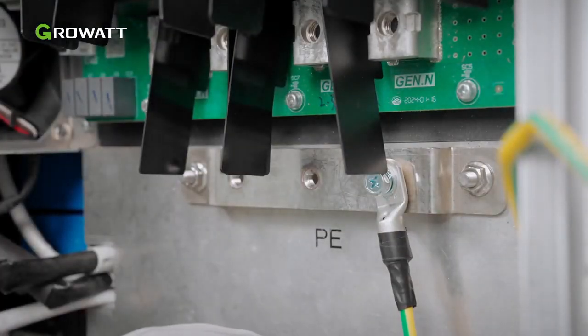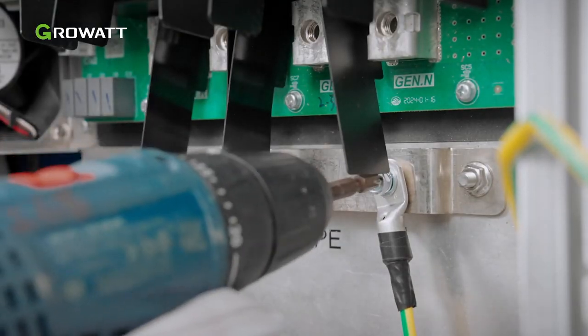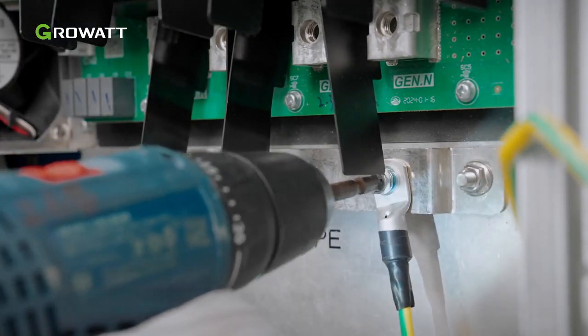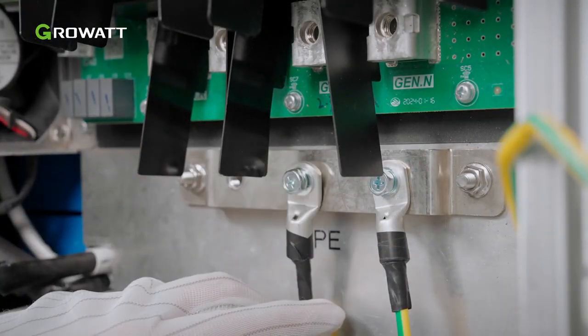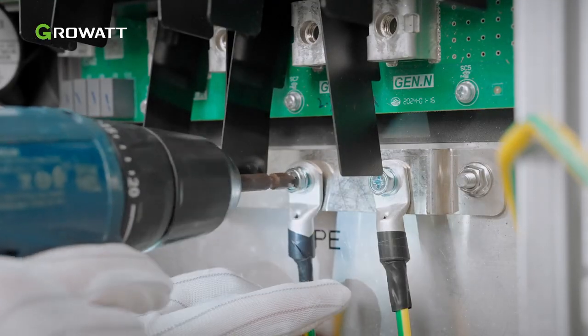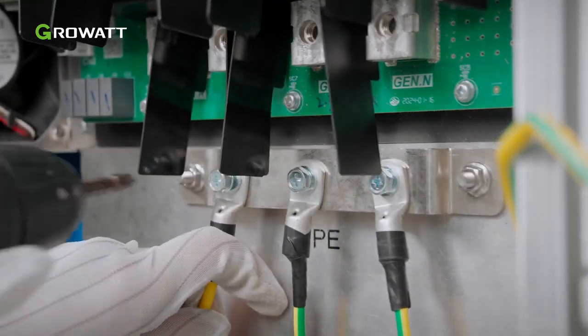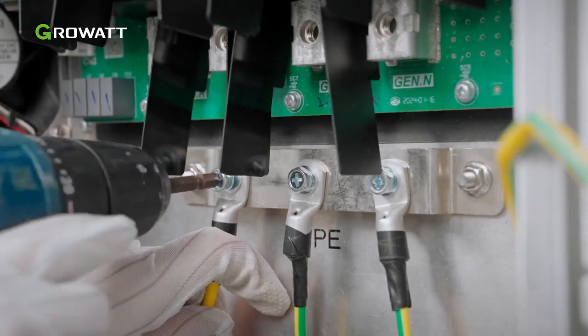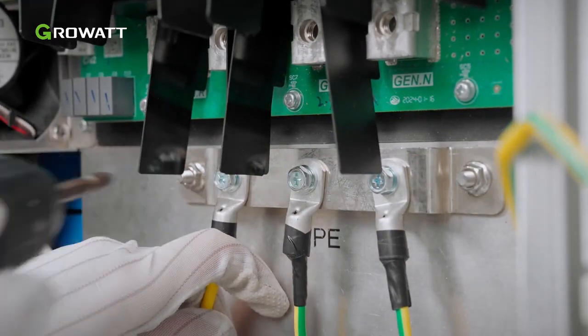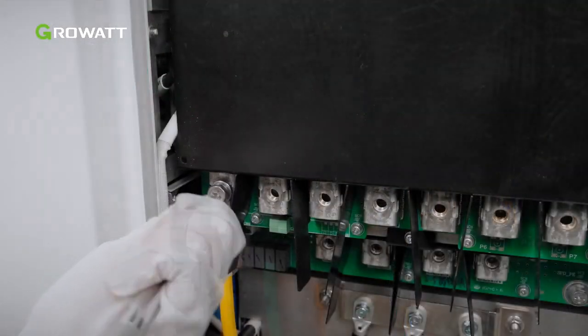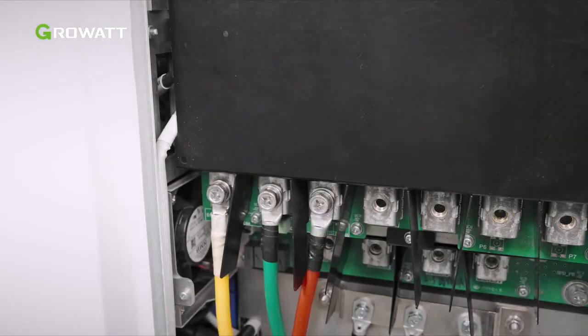First, connect the ground cable to the copper grounding bar inside the right cover plate. Then connect the AC cables at the load port. Please note that the number of grounding cables to be connected should not be less than the number of AC port sets to be connected to the system. Connect the AC cable to the load port.